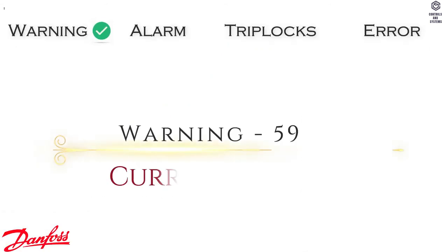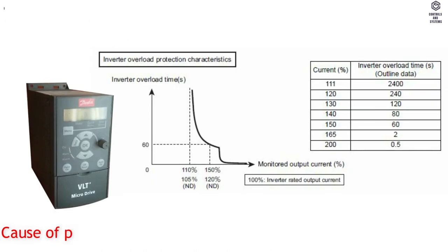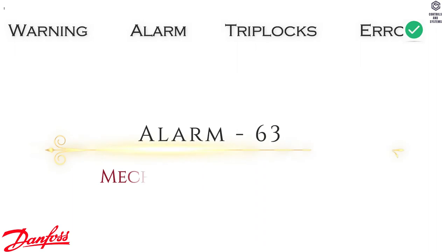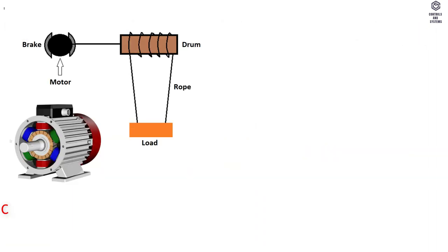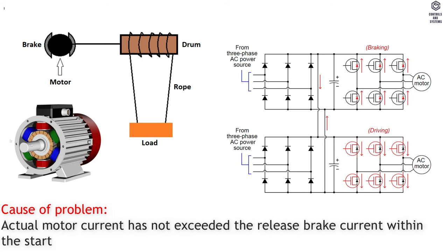Warning 59: Current Limit. Cause of Problem — frequency converter overload. Alarm 63: Mechanical Brake Low. Cause of Problem — actual motor current has not exceeded the release brake current within the start delay time window.